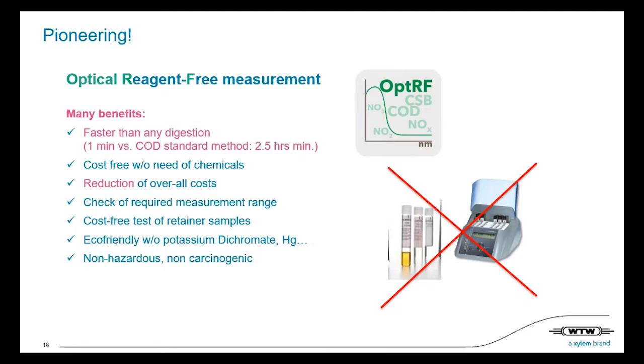You should always do a slow cooldown, because then all turbidity settles and you don't get disturbance and inaccurate values from too much turbidity from the digestion process. So it's faster than any digestion, and it's cost-free — you don't need any chemicals to read it. This means a reduction of overall costs.